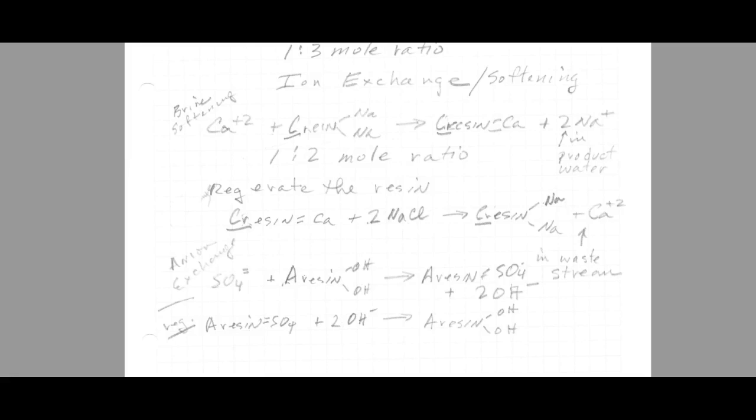You regenerate the resin with salt brine solution. So it takes 2 moles of sodium chloride to release 1 mole of calcium. Then the calcium ends up in the rinse water that goes to waste.